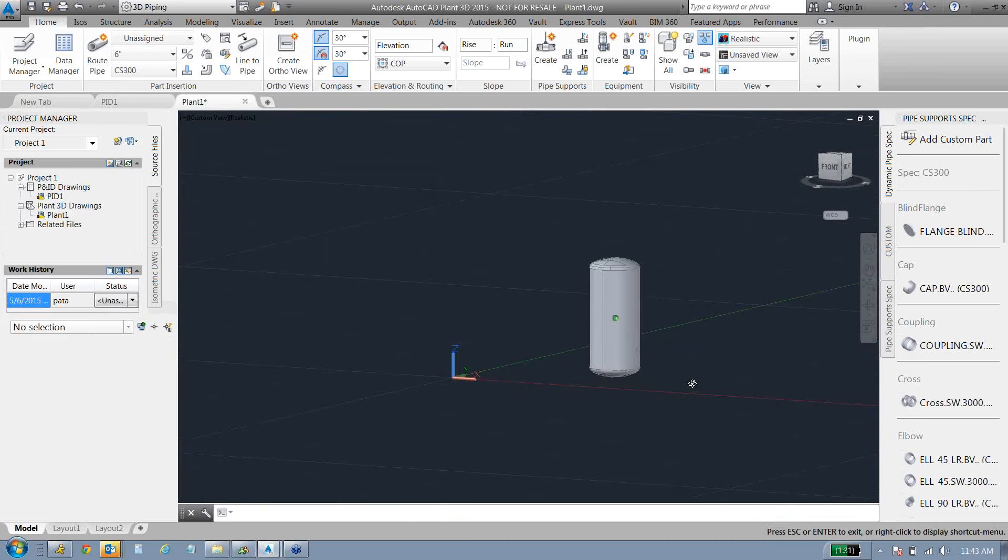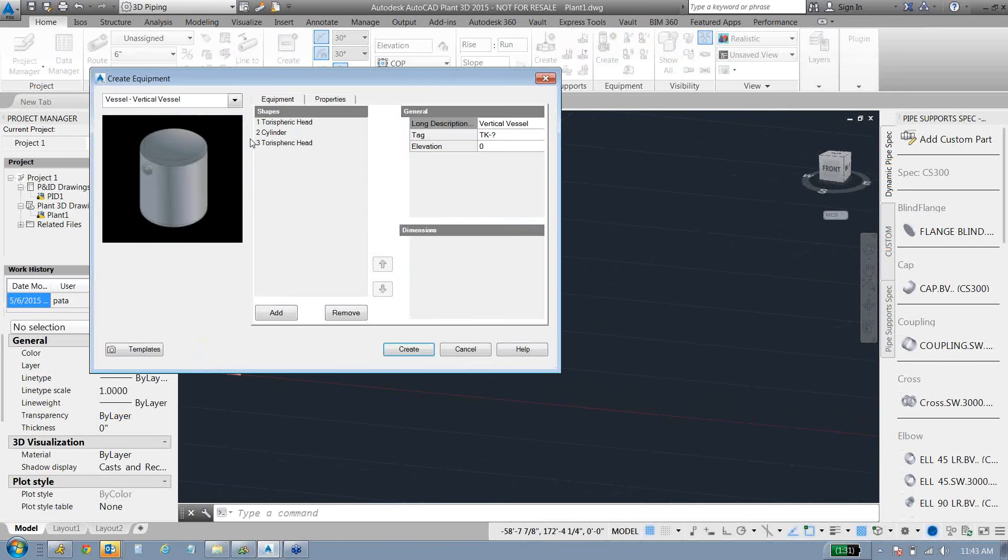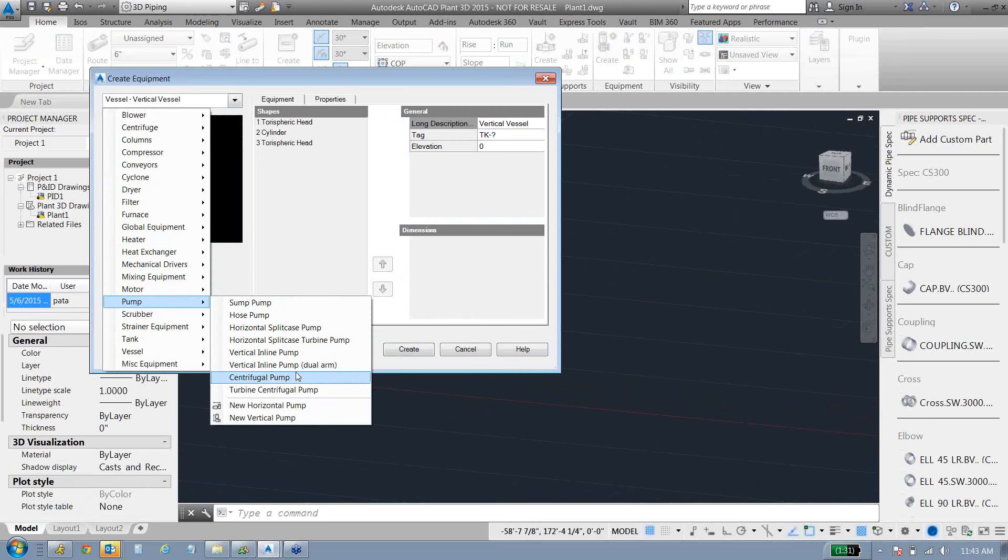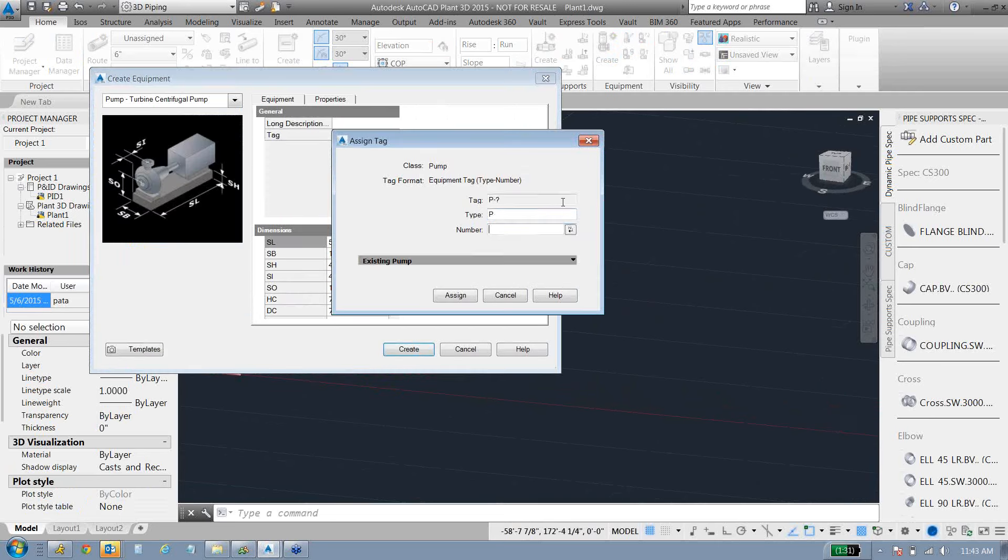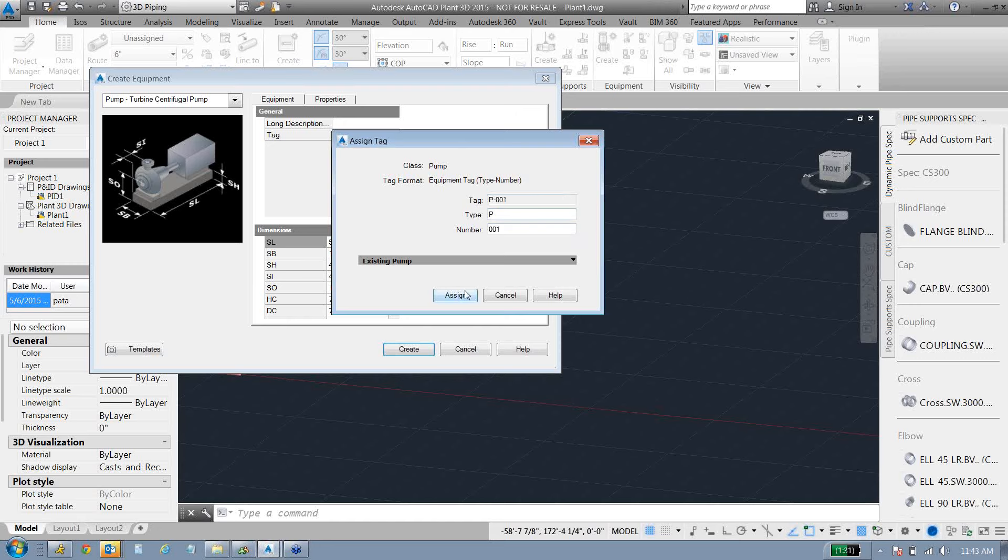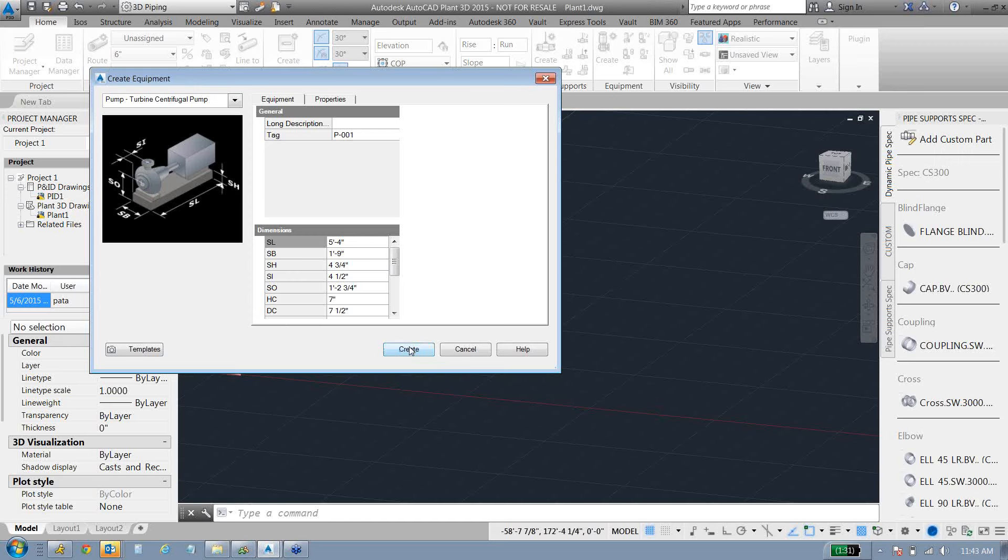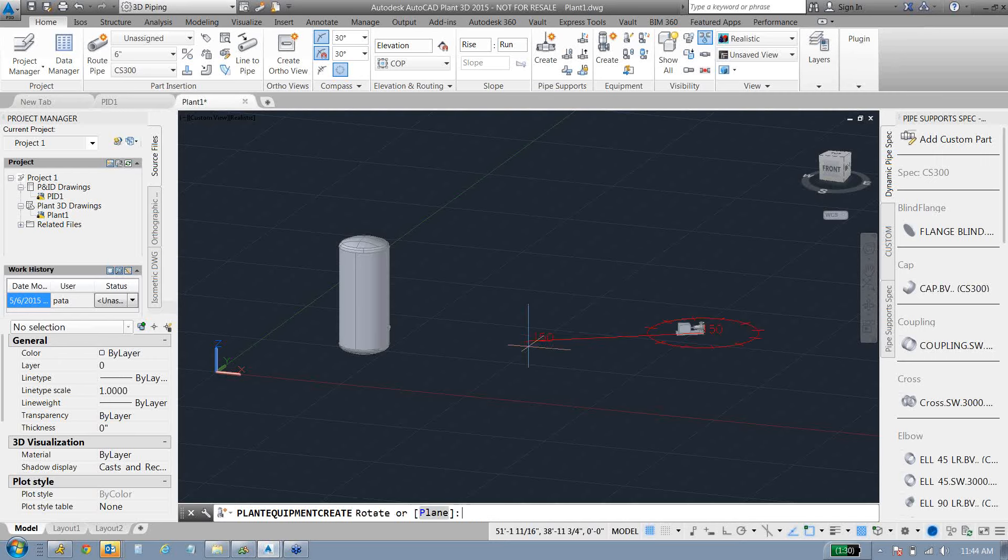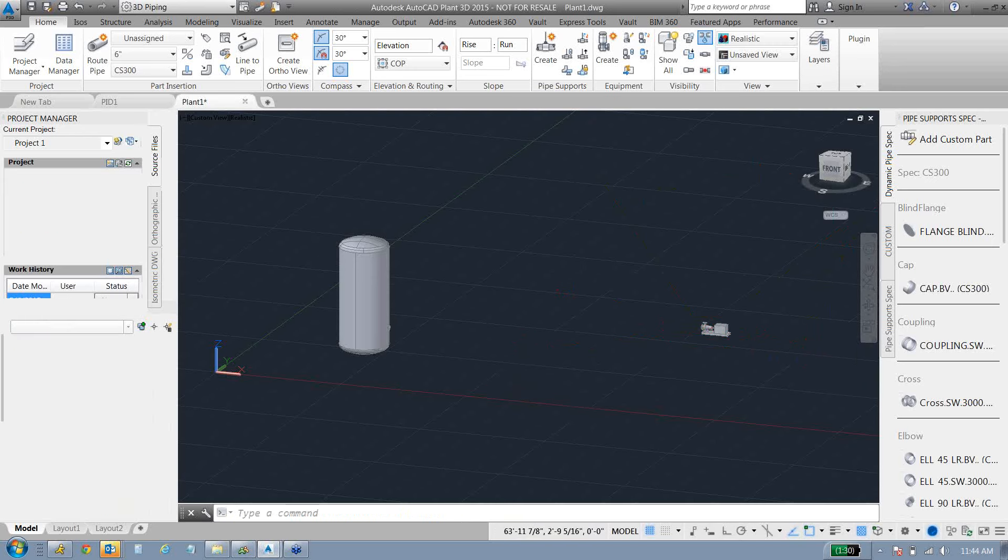These nozzles are completely editable. My line on the P&ID was a six inch, 300 pounds. So we'll turn that flange up to 300 pounds, six inch. We can also change where it is relative to the piece of equipment. So you can move that nozzle up or down or angle it differently. Lengthen the pipe a little bit.